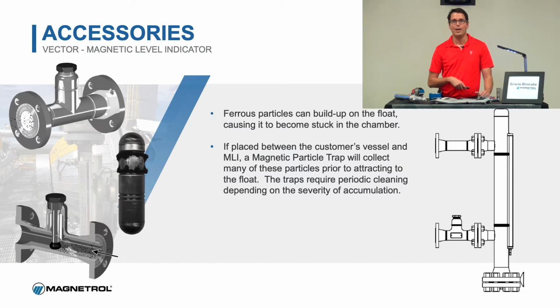There we go. One more accessory on these guys. And if you get into the case of an older vessel and you're connected to an older vessel, those are going to typically have corrosion inside of the tank. And that corrosion may accumulate on the magnets of the float, as you can see here, because they're ferromagnetic. So most tanks are carbon steel. And if they corrode, those filaments will stick to the float, weighing it down over time.